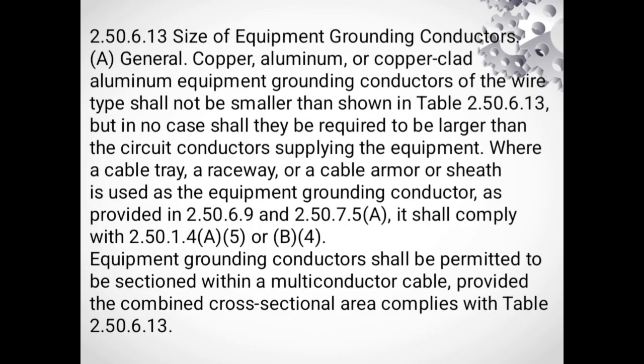2.50.6.13 Size of equipment grounding conductor. A. General. Copper, aluminum or copper clad aluminum equipment grounding conductors of the wire type shall not be smaller than shown in Table 2.50.6.13, but in no case shall they be required to be larger than the circuit conductors supplying the equipment. Where a cable tray, a raceway, or a cable armor or sheath is used as the equipment grounding conductor, as provided in 2.50.6.9 and 2.50.7.5a, it shall comply with 2.50.1.4a 5 or B4. Equipment grounding conductors shall be permitted to be sectioned within a multi-conductor cable, provided the combined cross-sectional area complies with Table 2.50.6.13.